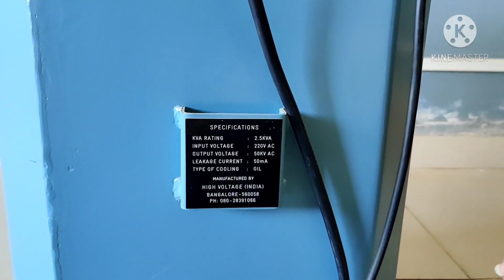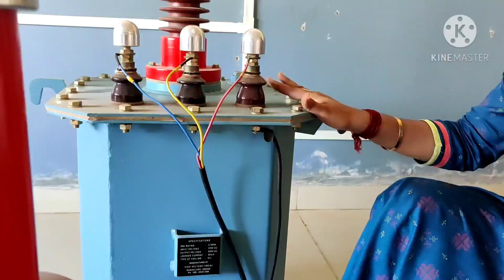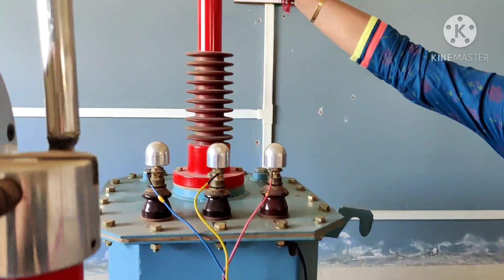So this kit converts 230 volt AC to 50 kilovolt AC. These are three live wires, R, Y and B, and we have the bushings. At this tip we have 50 kilovolt AC. 230 volt was my input, now that is given to this, and this tip has 50 kilovolt AC, which travels through this wire and connects to this.